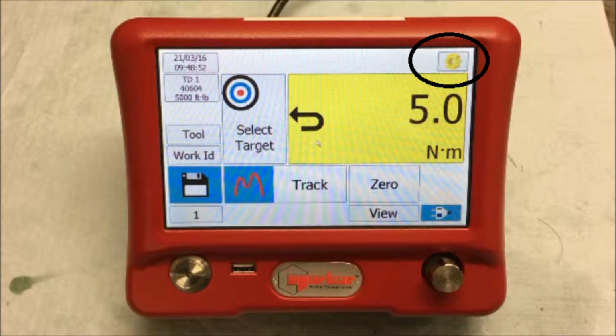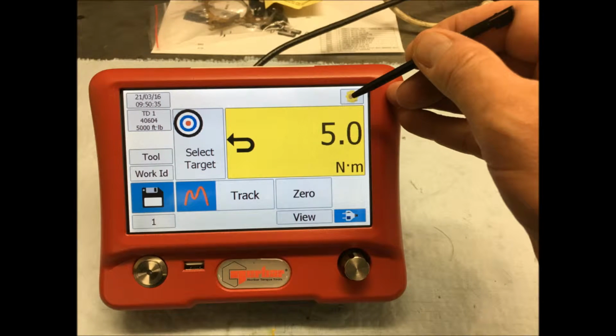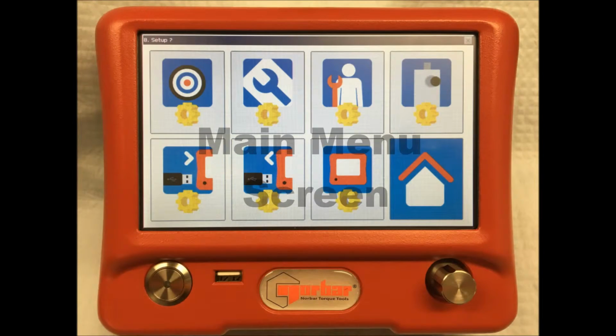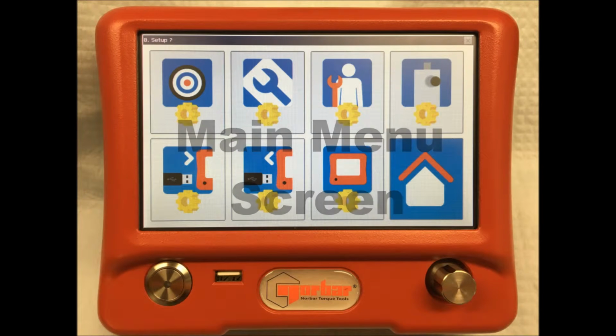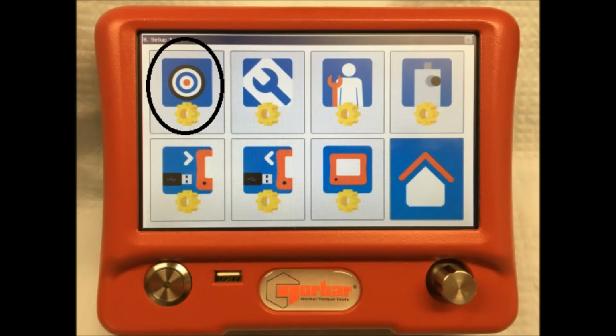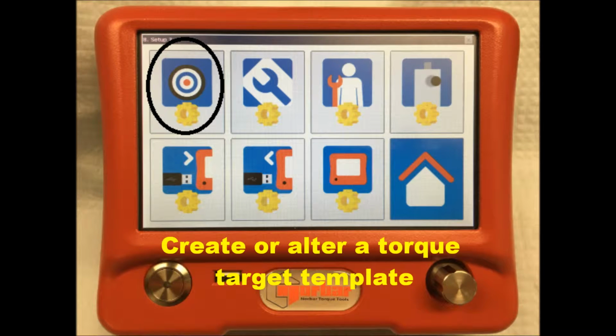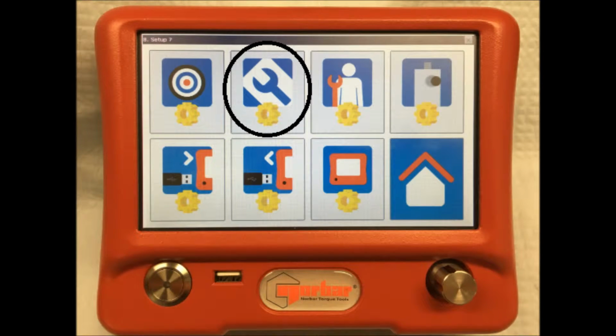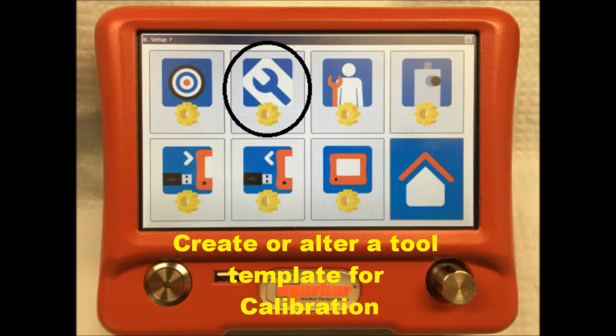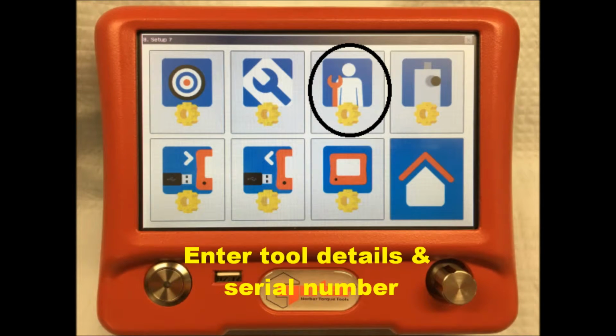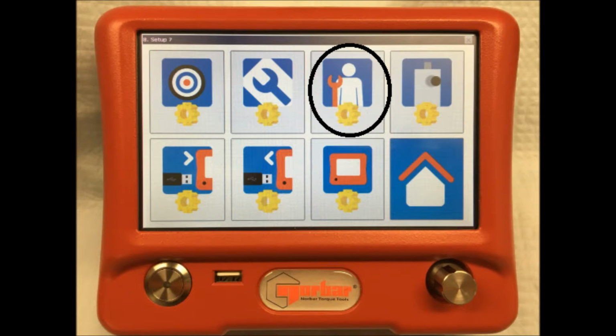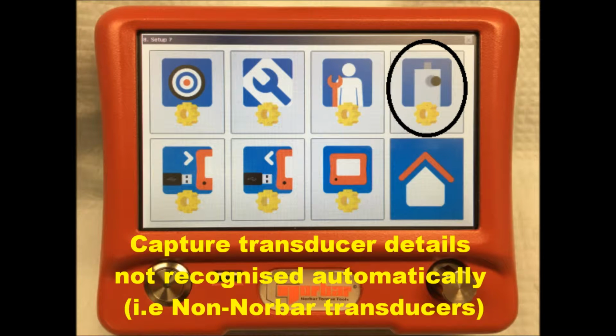By pressing the Settings function button on the top right hand side of the home screen, you'll be taken through to the main menu screen. The first function on the main menu screen is the target function that allows you to create or alter a torque target template. The second allows the operator to create or alter an existing tool template for calibration purposes. The third function allows the operator to capture the serial number and details for specific tools that are tested. The fourth function allows the user to capture the transducer details for transducers that are not automatically recognized by the software.